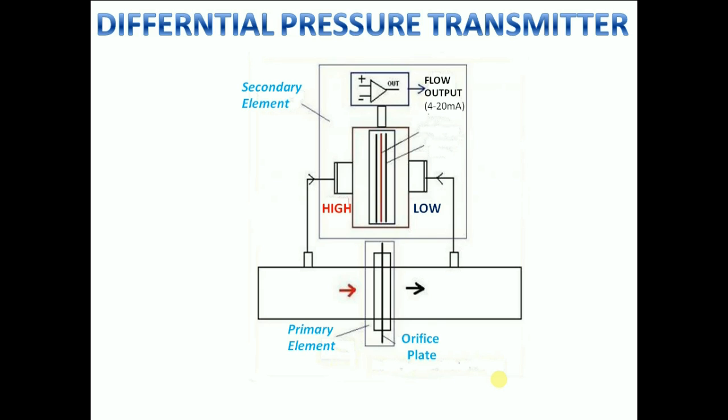The majority of industrial DP transmitters are fitted with diaphragm as the pressure sensing element. This diaphragm is a mechanical device. It is placed in between the two pressure inlet ports. The diaphragm will be deflected by the applied pressure. This deflection is converted into an electrical signal.